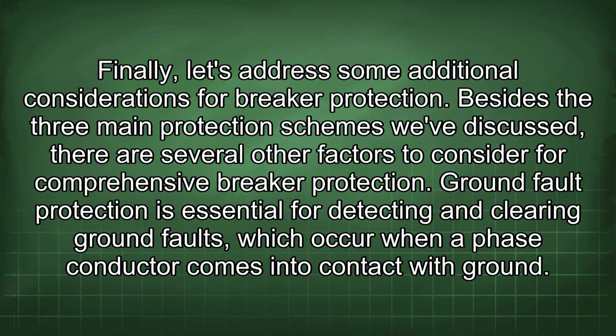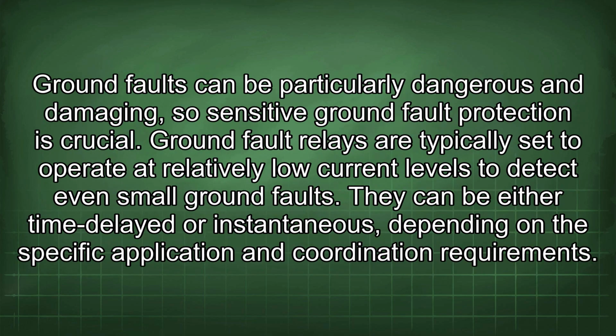Finally, let's address some additional considerations for breaker protection. Besides the three main protection schemes we've discussed, there are several other factors to consider for comprehensive breaker protection. Ground fault protection is essential for detecting and clearing ground faults, which occur when a phase conductor comes into contact with ground. Ground faults can be particularly dangerous and damaging, so sensitive ground fault protection is crucial. Ground fault relays are typically set to operate at relatively low current levels to detect even small ground faults. They can be either time delayed or instantaneous, depending on the specific application and coordination requirements.